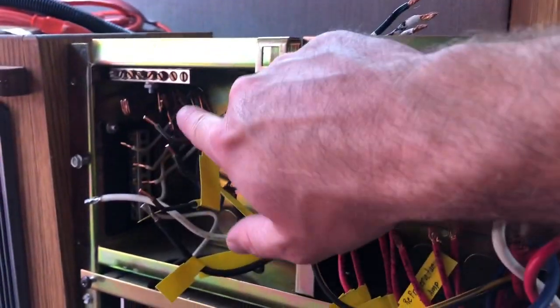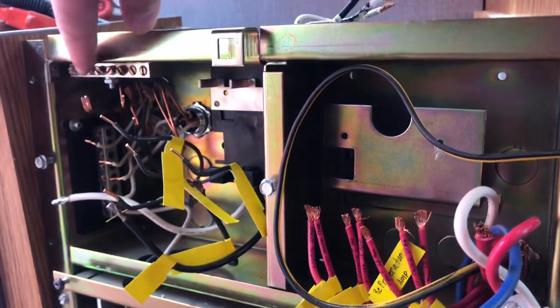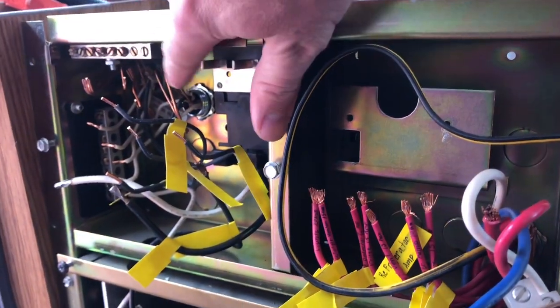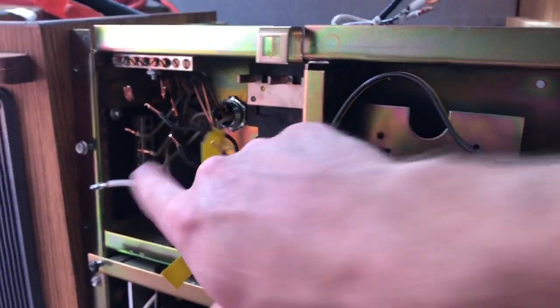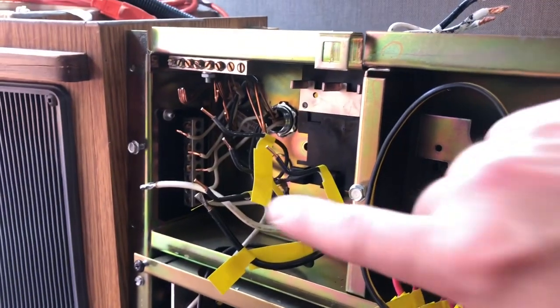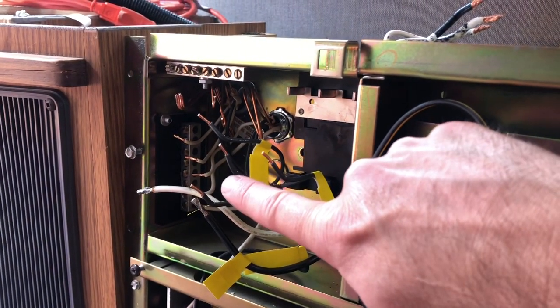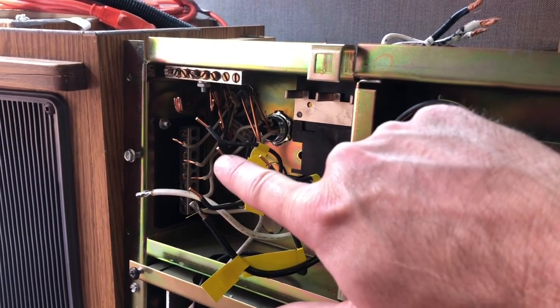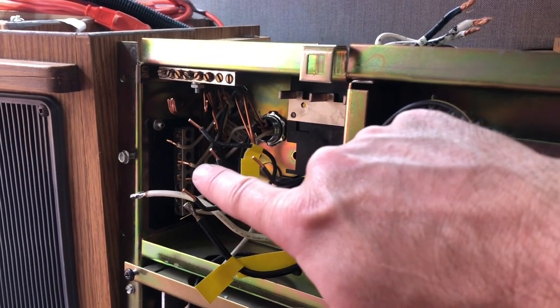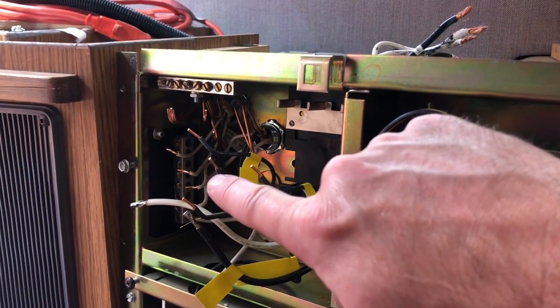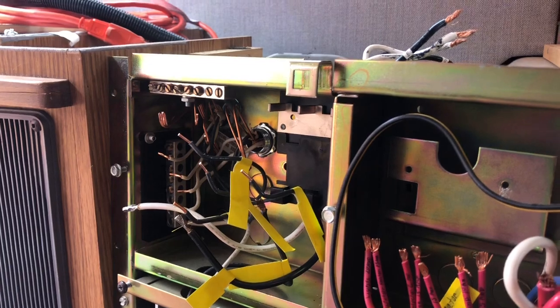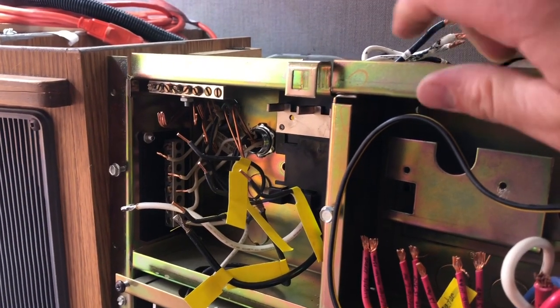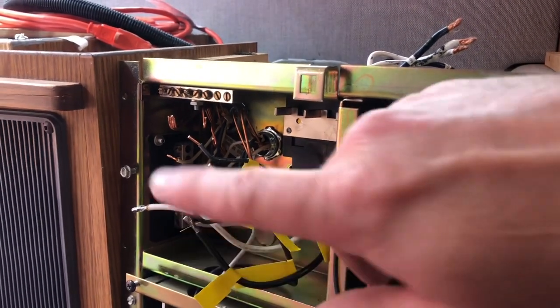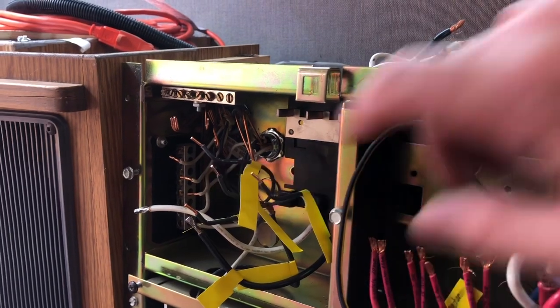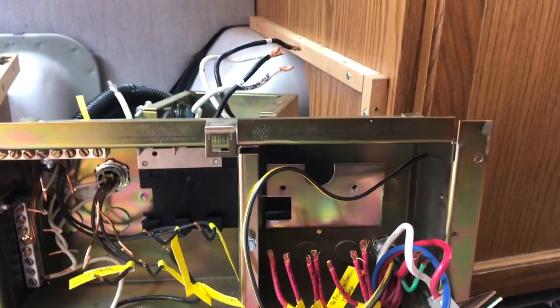Alright, so we got the grounds off, basically just unscrew those and pop them out, and then we got the neutrals off. A good thing to remember with the neutrals is that those are current carriers, so make very certain that you've got the shore power off and any other AC inputs off. Basically only shore power and generator, but make sure that if you're dealing with those, you're careful because they do carry current.